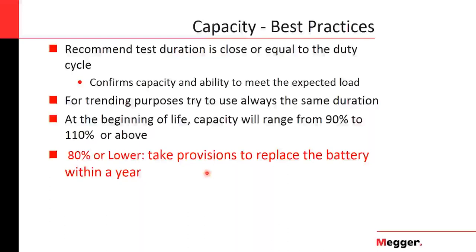So deciding the time has many factors involved. Try to always use the same time to be able to trend the values. Batteries have an efficiency associated with them, and the higher the current, the lower the efficiency, so you want to always use the same time for the discharge. Another thing: when you perform the test at the beginning of the life of the battery, you will have capacities ranging from 90 to 110%. In the previous example, you saw it was up to 133%. So it's common to see higher or lower values.